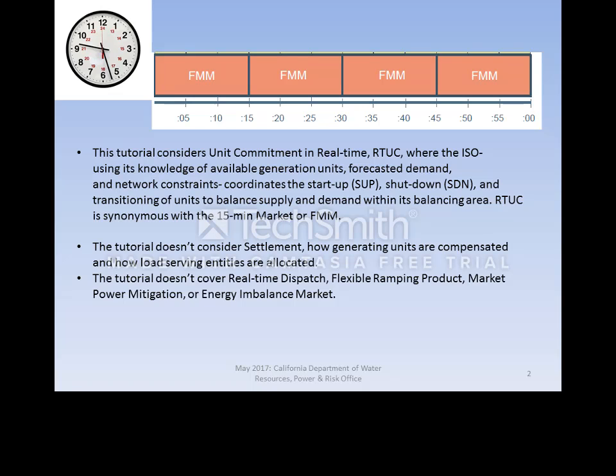The real-time market opens to bids of supply and forecasts of demand at 1300 or 1 PM the day prior to the trading day, or when the day-ahead market results are published. The real-time market closes 75 minutes before the trade hour. Energy and ancillary services required to serve load and balance the grid are produced by generation units. In the event of a grid disturbance or a scarcity of imbalance energy supply, the ISO manages grid stability by converting ancillary services capacity into energy in real time.